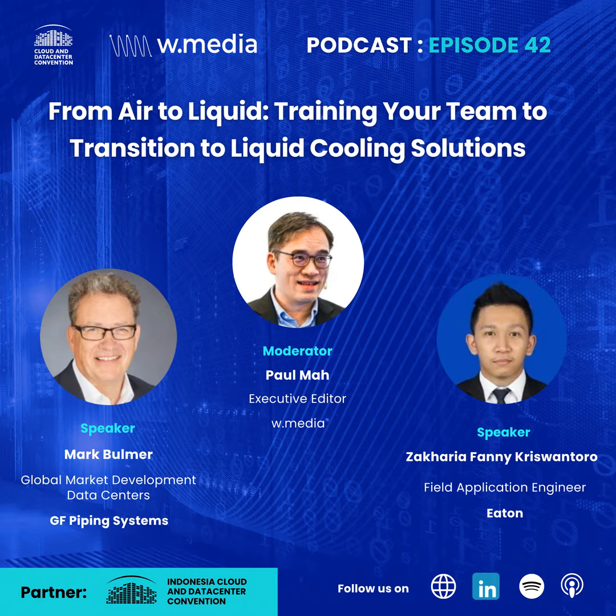So we use much lower speeds to allow for future proofing, so down the road the piping system can cope with higher demand by slightly increasing the flow speed of the coolant. We design the initial piping system at a low speed - I'm talking about 0.8 to 1.2 meters per second - whereas normally for chilled water systems you're talking 1.5 to 2.5 meters per second, so a lot slower than normal. That gives you a larger piping system cooling capacity that can cope with future demands over the years, and also gives reliability in terms of flow through the manifolds in the rack.